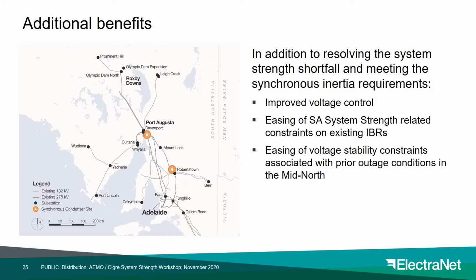In addition to resolving the system strength shortfall and meeting the synchronous inertia requirements declared by AEMO, installing synchronous condensers at the Davenport and Robertstown substations results in improved voltage control in the Mid-North region of the state, easing of SA system strength related constraints on existing inverter-based resources, and the easing of voltage stability constraints associated with prior outage conditions in the Mid-North region.